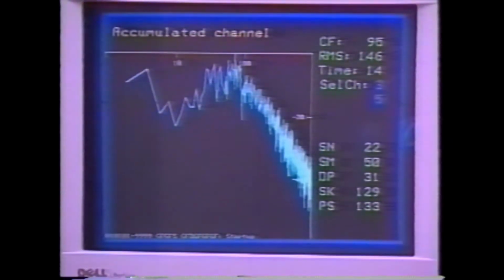All 8 EMG signals and the double subtracted signal are conditioned and converted into the frequency domain by a fast Fourier transform. An average power spectrum representative of 1 second of EMG is displayed for the double subtracted signal. A reference power spectrum in green can be selected and used for comparison to incoming spectrums. Center frequency and RMS values for the average power spectrum are displayed, as well as the channels which indicate where the diaphragm is located on the electrode array.